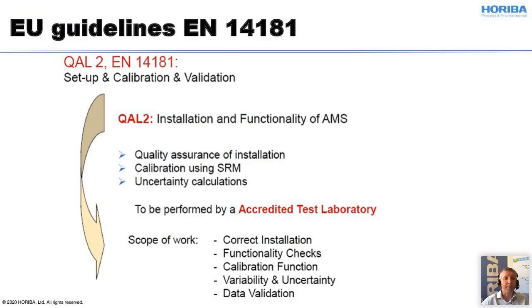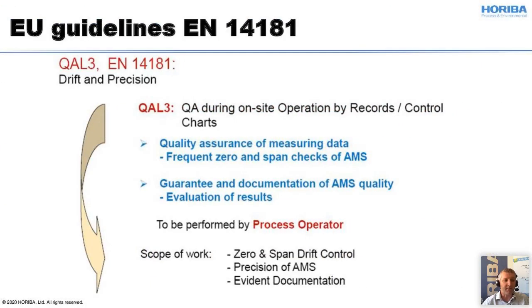Next step is the QAL2. Same standard, EN 14181. But the difference is we are no longer talking about a system which is in the laboratory. We are now talking about the setup and calibration and validation in the field at the customer site. That means after installation, the functionality of the AMS will be tested with the certain topics mentioned here on the slide. Next step is the QAL3, which checks and validates the drift and the precision of the installed instrument. The major difference to the two guidelines before is that the QAL3 procedure needs to be done by the process operator. That means the plant owner is responsible for taking care of this QAL3 procedure.